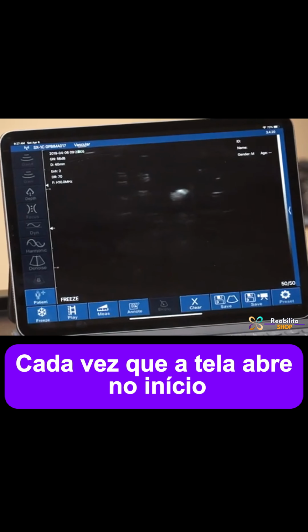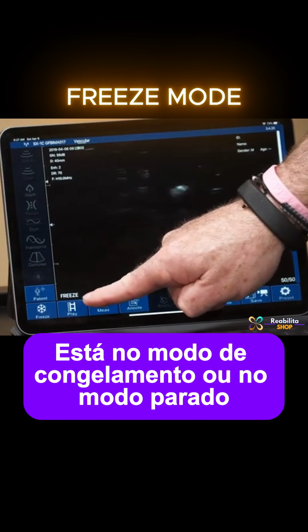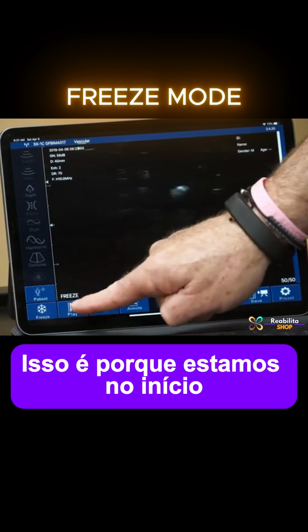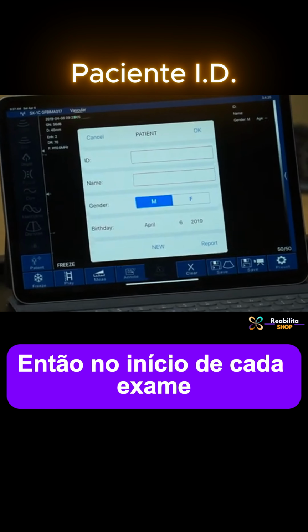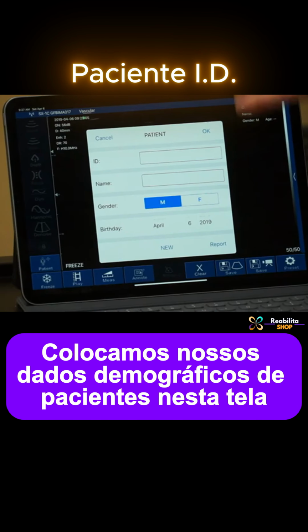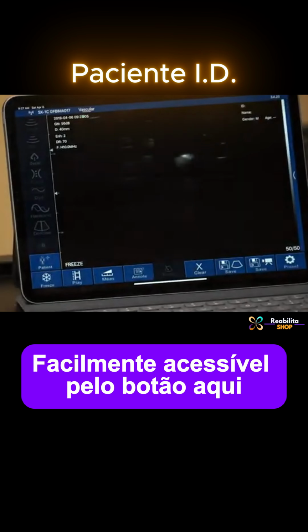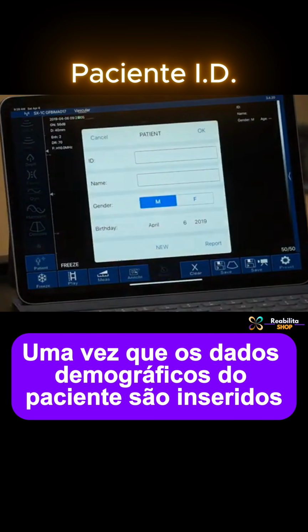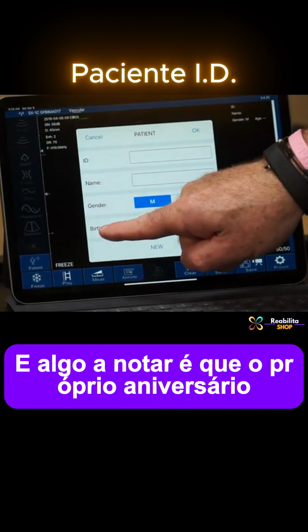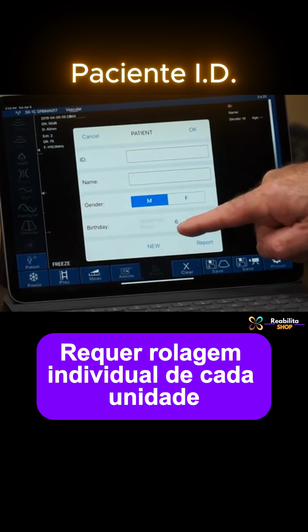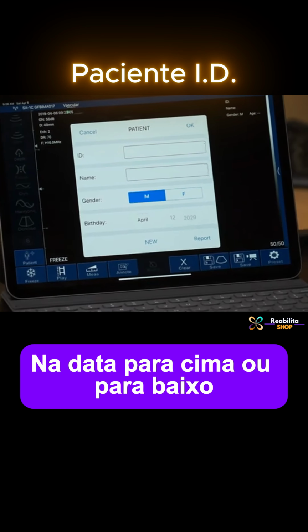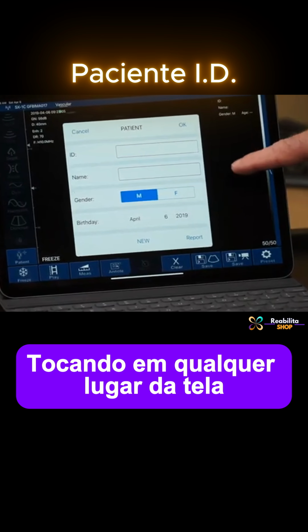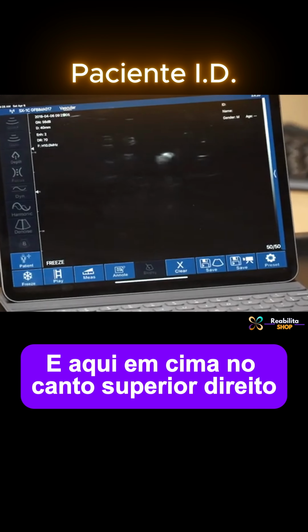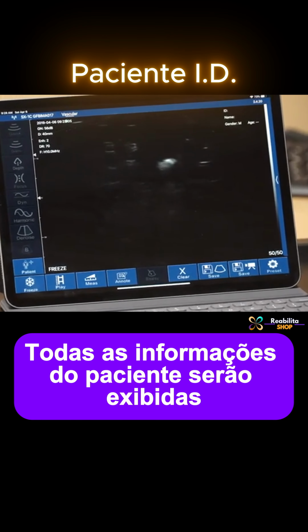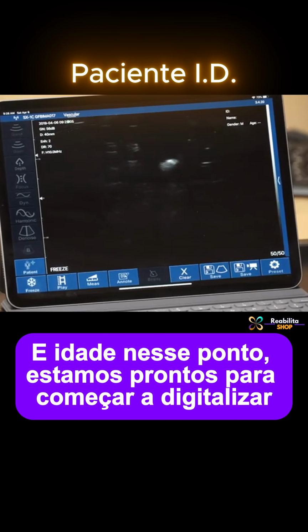Each time the screen opens at the very beginning, it's in the freeze mode or still mode. This is because we are at the very beginning, ready to enter patient information. So at the beginning of each exam, we put in our patient demographics on this screen, easily accessible by the button here. Something to note is that the birthday itself requires individual scrolling of each unit in the date, up or down. Once the demographics are entered, touching anywhere on the screen will leave that. And up here in the upper right-hand corner, all of the patient information will be displayed: the patient ID, name, gender, and age. At that point, we're ready to begin scanning.